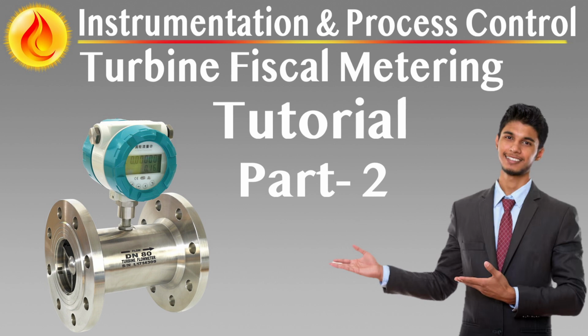Utility provisioning and infrastructure resilience. Electrical power architecture for system continuity. The turbine Fiscal metering system is categorized as a vital service load, demanding robust and redundant electrical infrastructure. Its continuous, failure-free operation is critical for custody transfer accuracy, contractual reporting, and regulatory compliance. To meet this, the power supply must include full duplication from the energy source through to the field instrumentation. This architecture eliminates single points of failure and supports uninterrupted flow measurement across normal, degraded, and recovery scenarios.